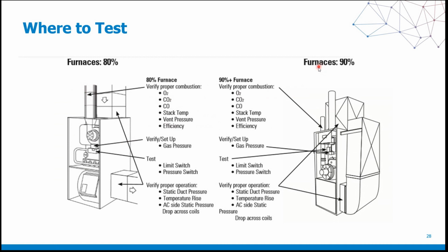When we talk about a 90% efficient furnace, obviously we want to measure our fresh air intake. We want to look at the quality of that fresh air intake. And then we want to take a test of our exhaust air as well. That's where we want to do our combustion test. That is where we want to evaluate the byproducts of our combustion, on our exhaust or our termination setup that we have. And make sure, obviously, that we don't have other things that are influencing both our fresh air intake and our exhaust when we talk about a high efficiency or a condensing type of system.